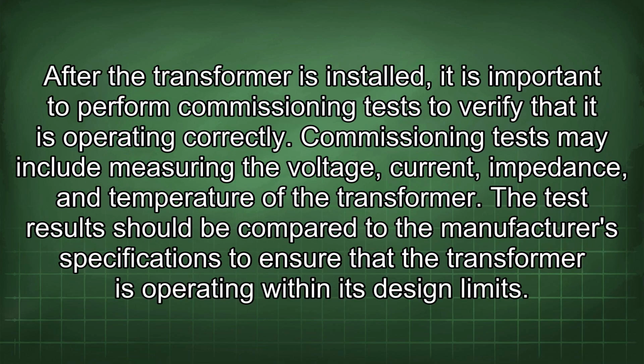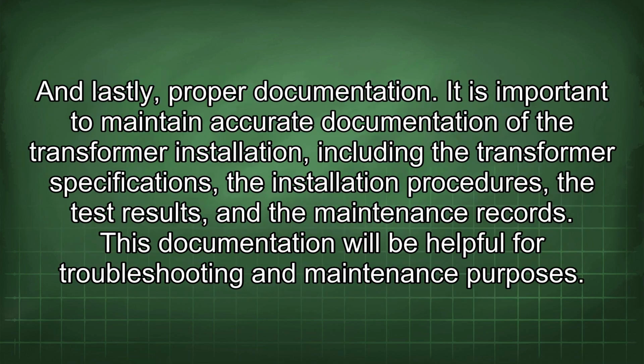After the transformer is installed, it is important to perform commissioning tests to verify that it is operating correctly. Commissioning tests may include measuring the voltage, current, impedance, and temperature of the transformer. The test results should be compared to the manufacturer's specifications to ensure that the transformer is operating within its design limits. And lastly, proper documentation.